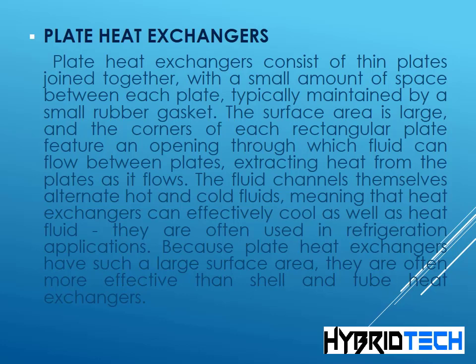Plate heat exchangers consist of thin plates joined together with a small amount of space between each plate, typically maintained by a small rubber gasket. The surface area is large and the corners of each rectangular plate feature an opening through which fluid can flow between plates, extracting heat as it flows. The fluid channels alternate hot and cold fluids, meaning that heat exchangers can effectively cool as well as heat fluid. They are often used in refrigeration applications. Because plate heat exchangers have such a large surface area, they are often more effective than shell and tube heat exchangers.